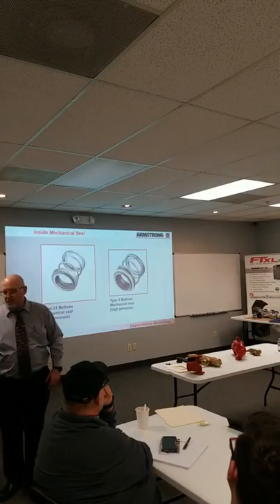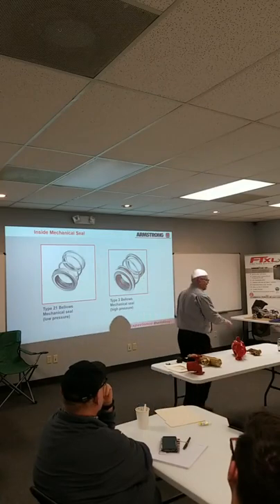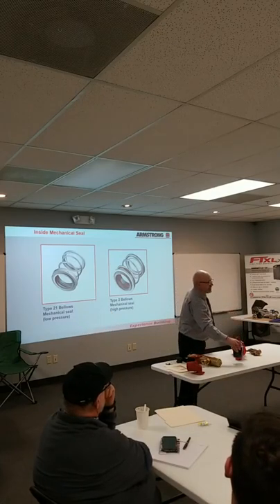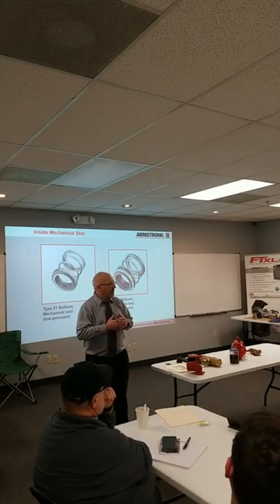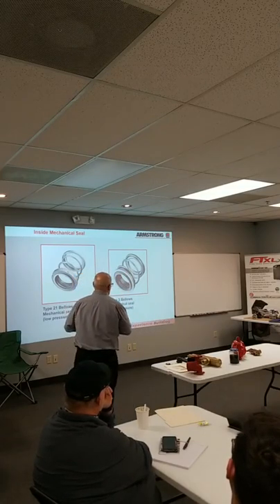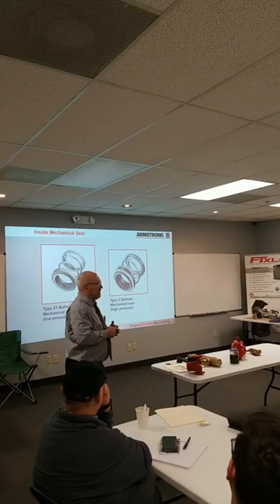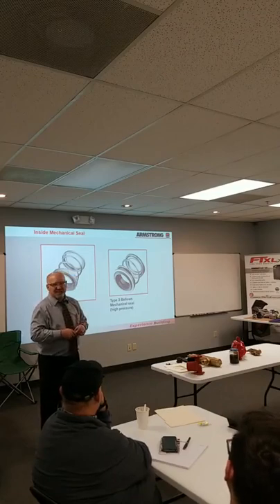Okay? And the worst thing in the world with pumps is seals. And this is the cause of it. Don't blame my seal. Don't blame the other guy's seal. This stuff is magnetic, it's gritty, and it just tears the living daylights out of seals. That's what it does to your hands. You can't get it off your hands. That's what kills pumps, and it's also killing your boilers, your controls, your valves, whatever you're using. So I preach about cleaning water systems. But again, they never seem to get done.